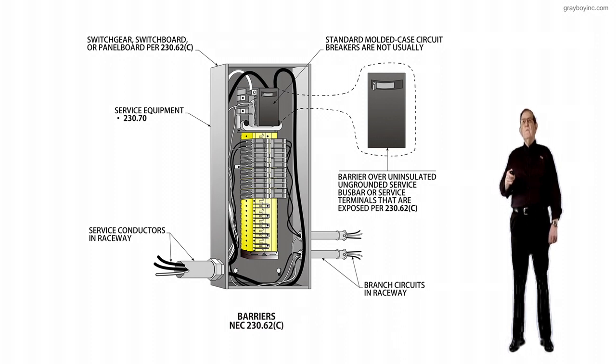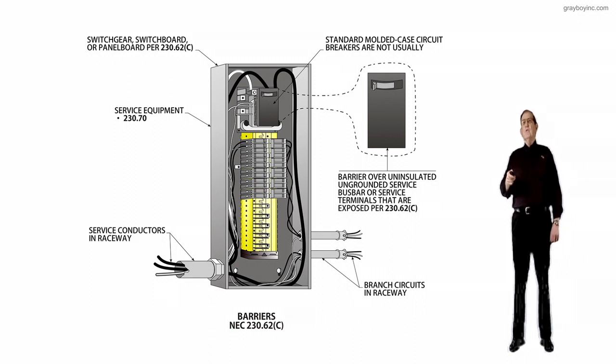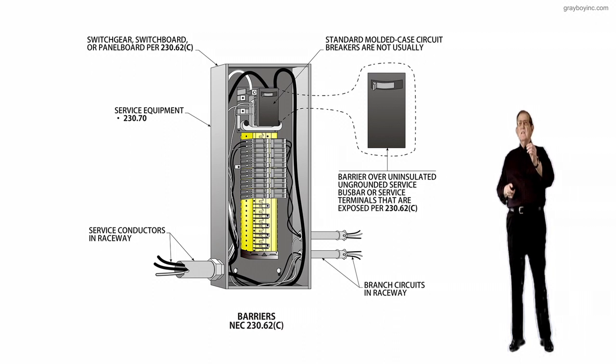They don't want this exposed because I can turn this off or de-energize this breaker, and then notice everything down here is de-energized. And I'm not going to expose a homeowner, a commercial facility manager, or a maintenance person to live energized conductors here, per NFPA 70B and NFPA 70E.